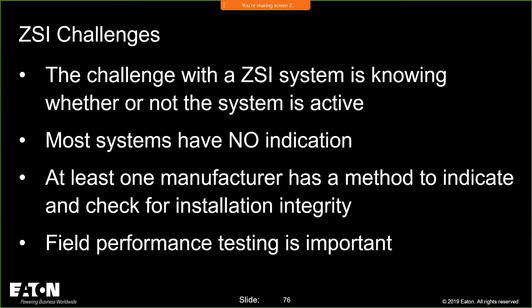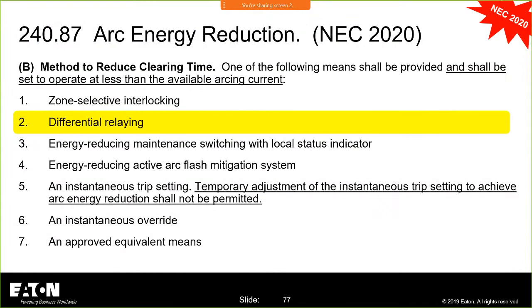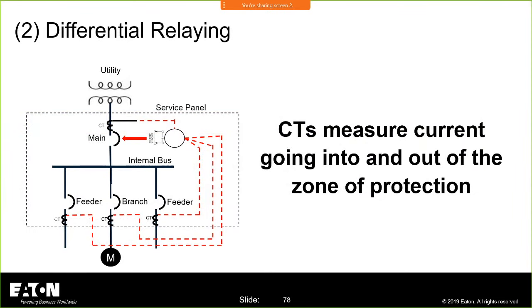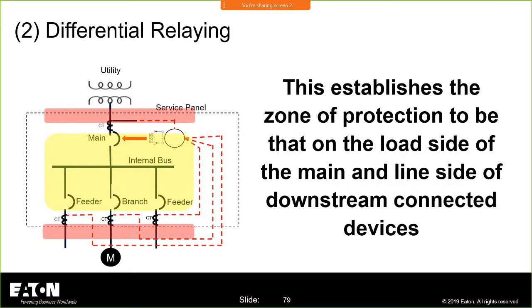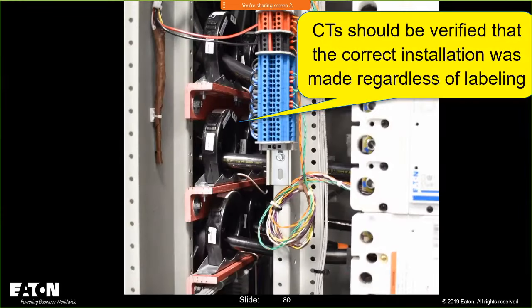All right. So this challenge is knowing that it's actuated. We have a system right now. Eaton, I think, is the only one who has an activation. So we'll give you indication that zone selective interlocking is working. And we have methods to test ZSI, because you have to do the performance testing at installation of all of these technologies I'm walking through right now. You're going to have to show that they are functioning. Differential relaying is the same thing that we talked about over on the 240.67. Same. The only difference is that you don't have ZSI when you're using fuses. And it's the same differential, so I'm not going to cover that again.